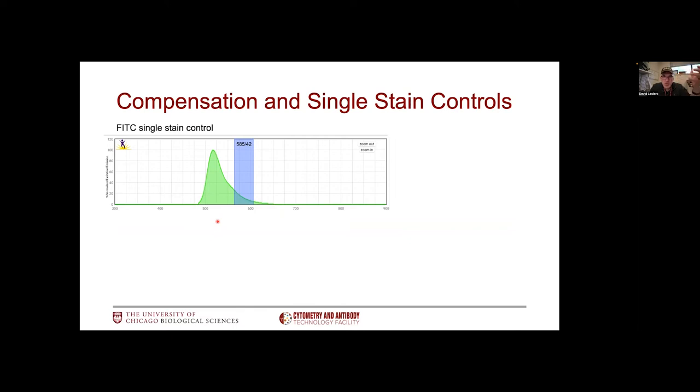To do proper compensation, we'll need single stain compensation controls. These are cells or beads stained with every single one of your fluorophores one at a time. You'll have as many controls as you have markers used in your assay. Compensation essentially is evaluating the impact of a specific fluorophore on the other detectors available on the instrument. We're trying to establish a situation where that fluorophore has no impact whatsoever.